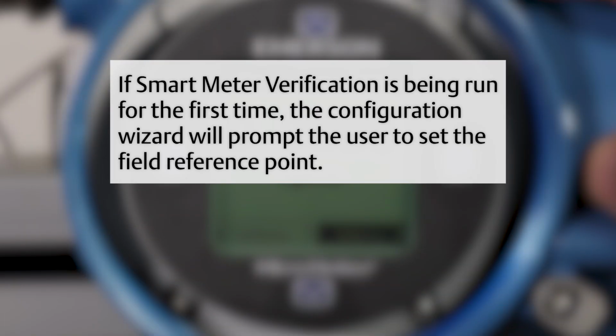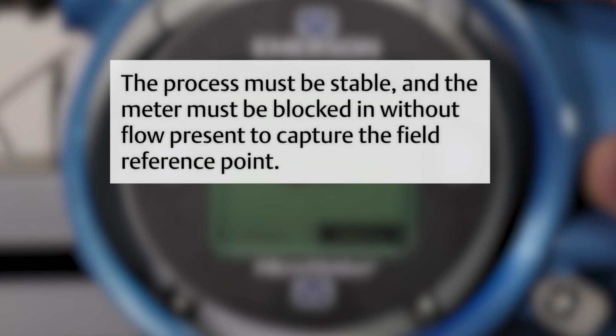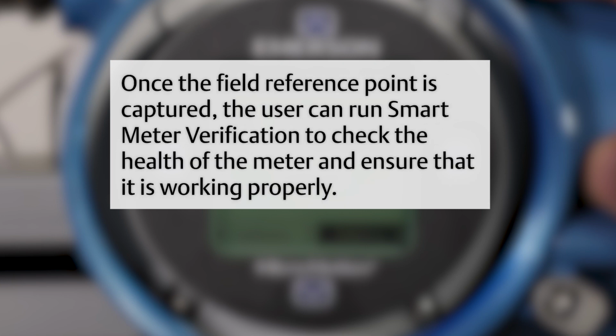If smart meter verification is being run for the first time, the configuration wizard will prompt the user to set the field reference point. The process must be stable, and the meter must be blocked in without flow present to capture the field reference point. Once the field reference point is captured, the user can run smart meter verification to check the health of the meter and ensure that it is working properly.